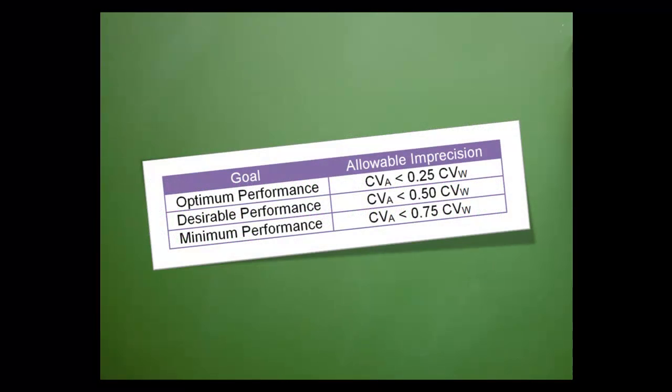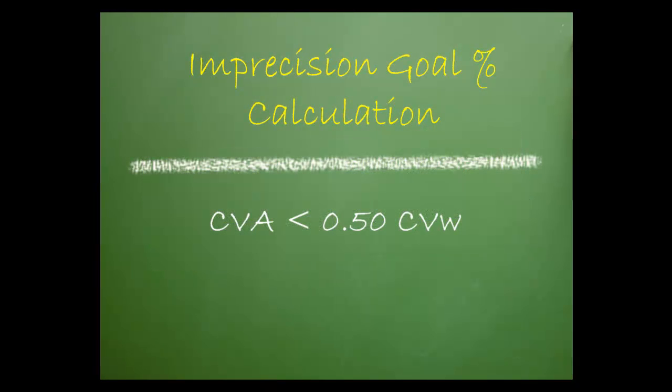Using the formula suggested by Dr. Frazier, allowable imprecision is calculated where CVA represents total allowable imprecision and CVW represents within subject biological variation as published. If we were to choose a performance goal for imprecision of desirable and the published CVW is 5.7%, then the CVA would be 2.85%.